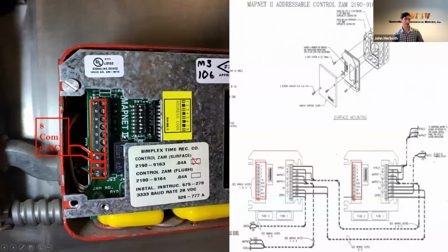So here's one that control ZAM here for that same project. And you start taking a look at the drawings, normally NC normally closed, NO for normally open. So you start taking a look at the contacts is where you are going to end up spending some time out in the field if you run into a problem. And for all these FSDs, unless it's involved in smoke ventilation, they should be normally closed. So they power open and normally close.